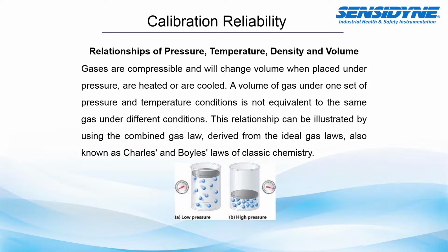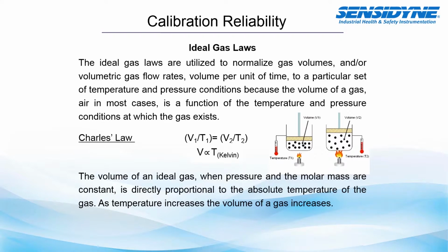So we'll talk a little bit about some of these laws and how they will relate or impact your air sampling calibration. The ideal gas laws are utilized to normalize gas volumes and/or volumetric gas flow rates. This is a volume per unit of time to a particular set of temperature and pressure conditions, because the volume of gas, of air in most cases, is a function of the temperature and pressure conditions at which the gas exists.